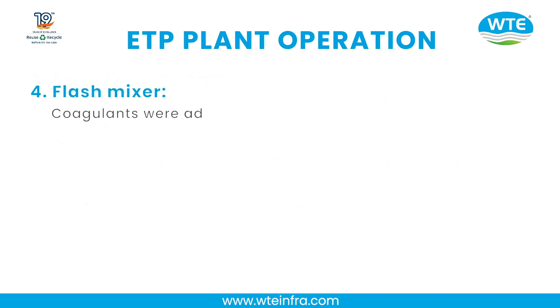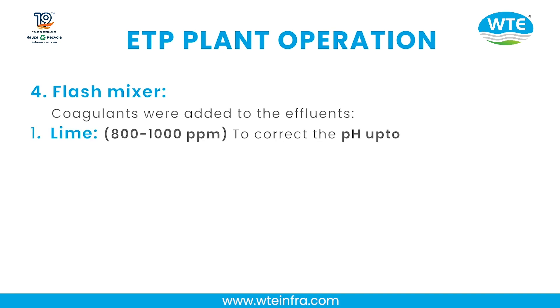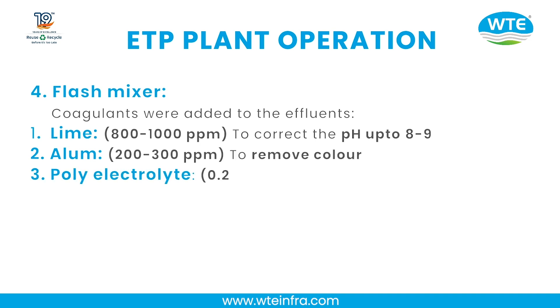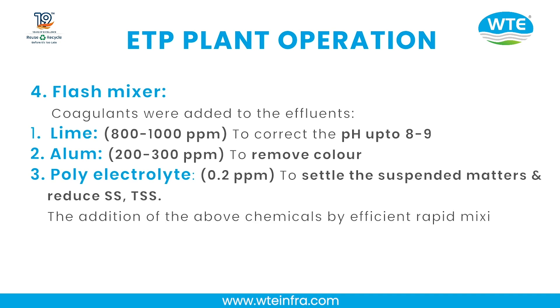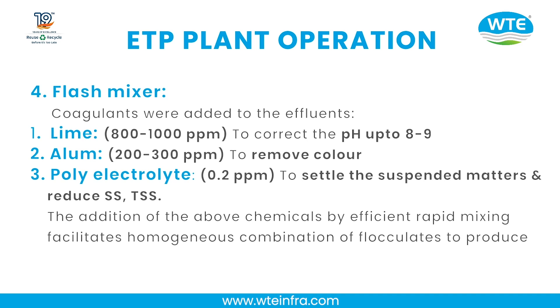Step 4 — Flash Mixer: Coagulants are added to the effluents: (1) Lime at 800–1000 ppm to correct the pH to 8–9; (2) Alum at 200–300 ppm to remove color; (3) Polyelectrolyte at 0.2 ppm to settle suspended matter and reduce TSS. The addition of these chemicals by efficient rapid mixing facilitates homogeneous combination of flocculants to produce microflocs.